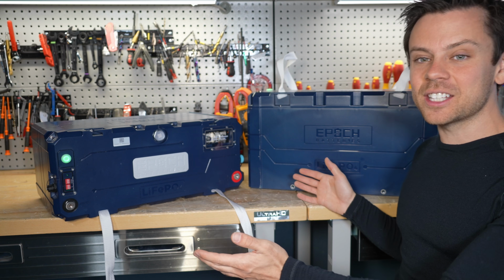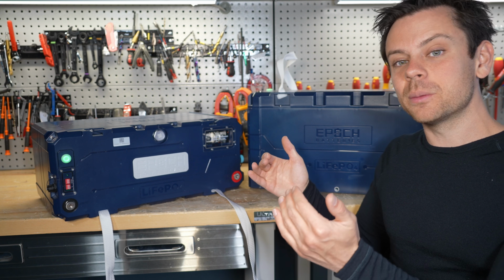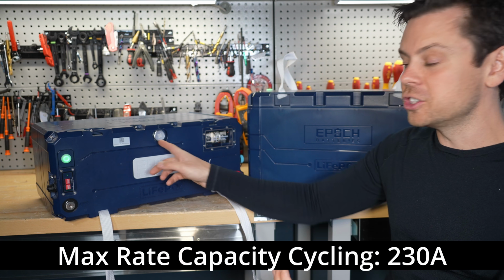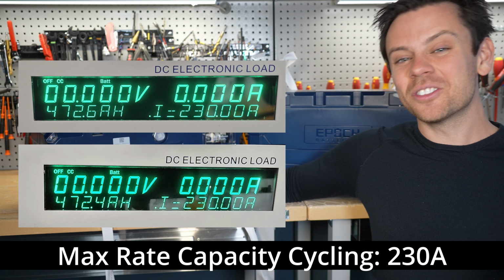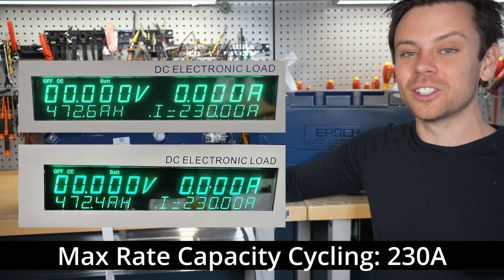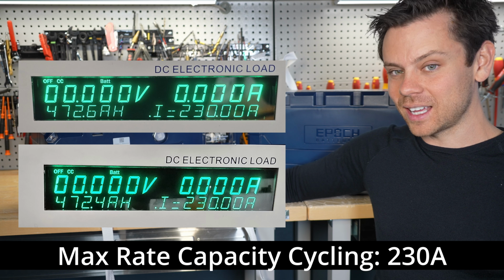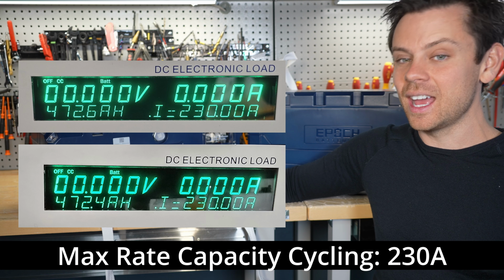Now the capacity tests were at 100 amps, and then I stepped it up to its maximum rated output of 230 amps. I had to do this manually with an electronic load and a large charger, and it also passed that test, and it passed the capacity at that rate.